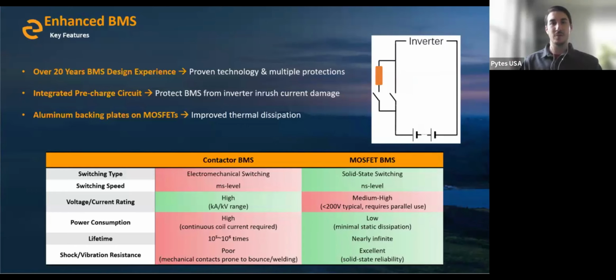The V10, like our other low voltage solution, employs a MOSFET BMS rather than a contactor BMS. A MOSFET BMS, you can kind of think of it as like an electronic gate or a valve that isn't necessarily physically opening or closing, but it's just changing state to allow current or voltage to pass through or not in response to signals sent by the BMS. So when we compare those 2 types of battery management systems together, and going back a step to explain that a bit, the BMS, the battery management system, essentially protects the battery from operating outside of its rated limits, right? So the BMS is monitoring the temperature, the voltage, the current in and out, not just of the battery on a pack level, but also down to each cell level.